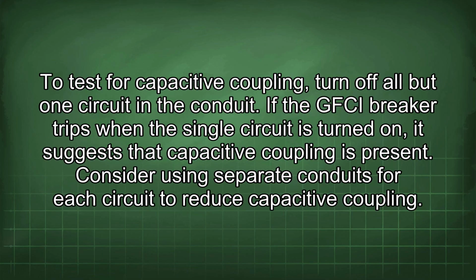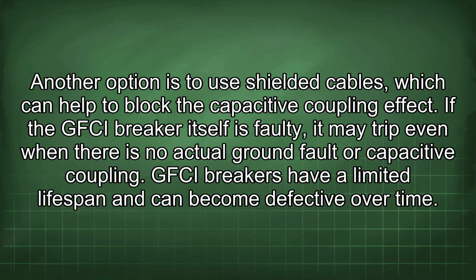To test for capacitive coupling, turn off all but one circuit in the conduit. If the GFCI breaker trips when the single circuit is turned on, it suggests that capacitive coupling is present. Consider using separate conduits for each circuit to reduce capacitive coupling. Another option is to use shielded cables, which can help to block the capacitive coupling effect.